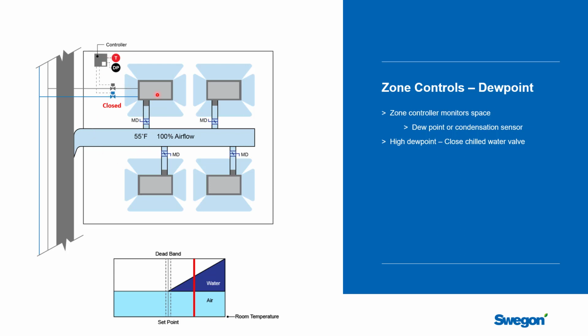Now, this will solve the problem about whether or not these beams are going to sweat and start dripping on the floor, but you've also just turned off the air conditioning in a control zone that almost certainly needs air conditioning. So while it's protecting the building, it is not helping the occupants at all. And so it is a good, kind of crisis level backup system, but it is not going to satisfy the occupants of the space very well.